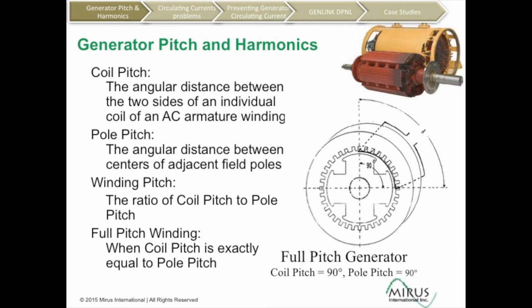So we can see the coil started at this location and then wound a full 90 degrees. This would be a full 100% coil pitch. Pole pitch is the angular displacement between the magnetic poles of the rotor or whatever is rotating that magnetic field. For a 4-pole generator, the angular displacement is 90 degrees. A full pitch generator is going to be one where the coil pitch, like a 4-pole full pitch generator, is going to have a coil pitch of 90 degrees, which matches the pole pitch of 90 degrees, and the ratio being 1.